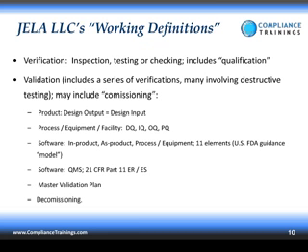Validation, I would define, well, let me read the definition here and then you determine whether you need further to it. It's under G in 820.30. Each manufacturer shall establish and maintain procedures for validating the device design. Design validation shall be performed under defined operating conditions on initial production units, lots, or batches, or their equivalents. Design validation shall ensure that devices conform to defined user needs and intended uses, and shall include testing of production units under actual or simulated use conditions. Design validation shall include software validation and risk analysis.